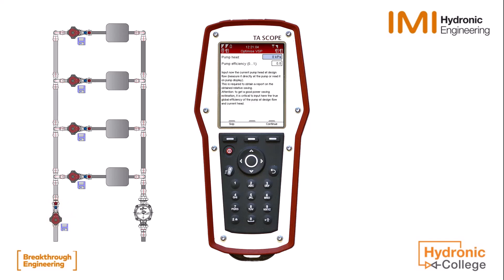You must now enter the current operational conditions of the pump. Pump head can be read on the pump screen or measured across the pump directly. Efficiency will need to be taken from the pump's data curve. These figures are required to enable TA Scope to give an estimation of energy savings from the VSP optimization process. Once you have entered the data, press Continue.